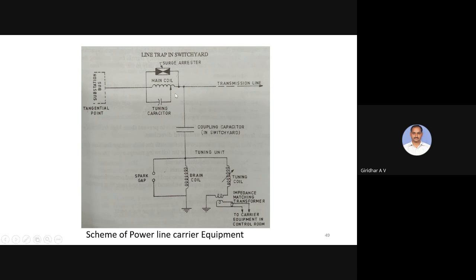Basically this main coil carries the full line current, and it is designed to carry normal current continuously with the temperature rise within the limits. Usually these coils are made in such a way that they will carry a short circuit current for a specified duration, like 1 second, that capability will be provided. In that way, it will have low self capacitance, and in higher frequency applications you can use it very well.